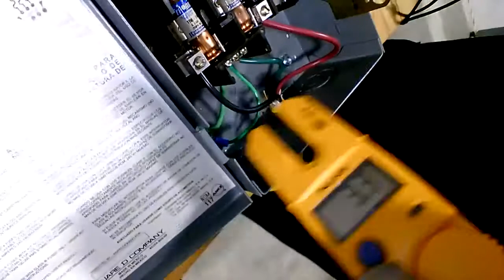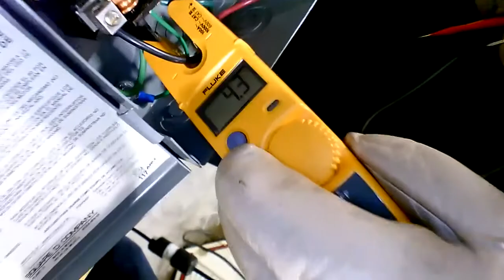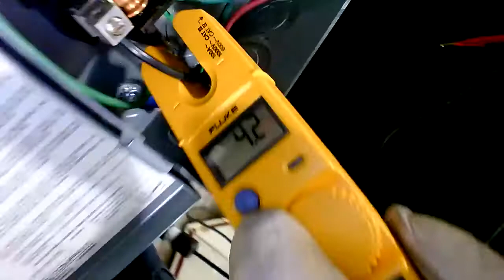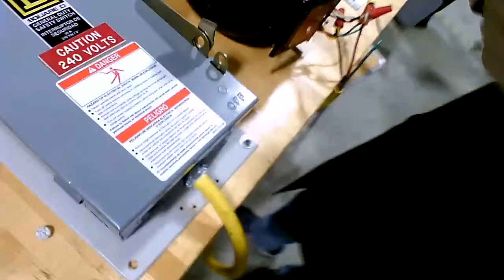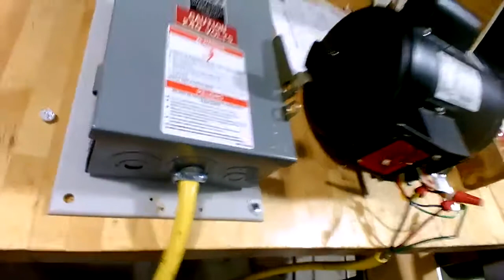That's good. Now let's check the amps. So you can change the meter over to A for amps. And you're going to get around each one of the motor leads with that fork. And you're reading 4.2 amps on that one. And 4.3 amps on the other one. Notice the wire has to be all the way up in the fork. That's good. Now shut that off. That was a way to check your incoming power going to your disconnect and leaving. And he was drawing 4.2 amps.